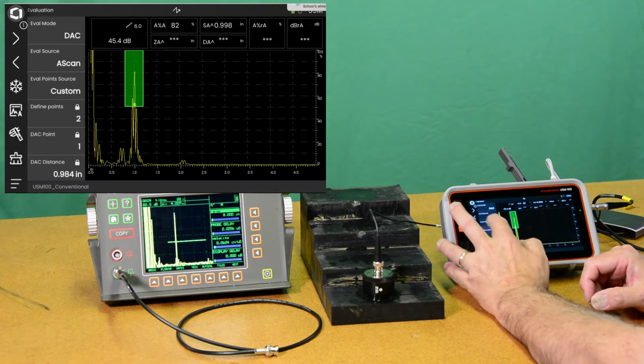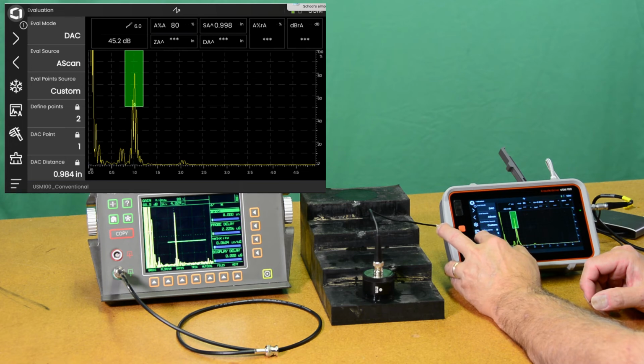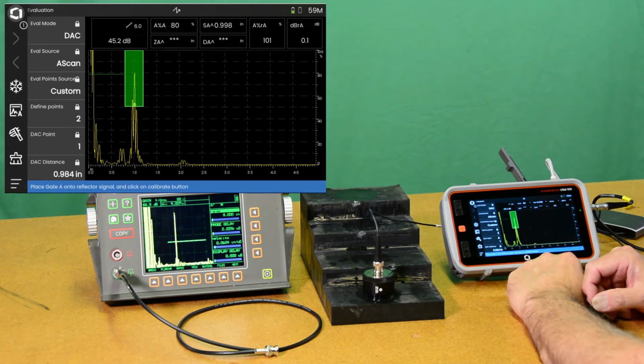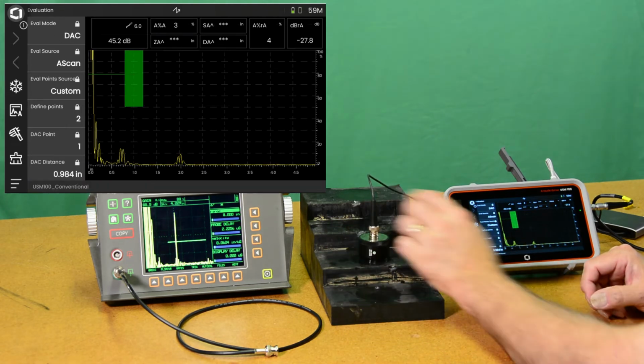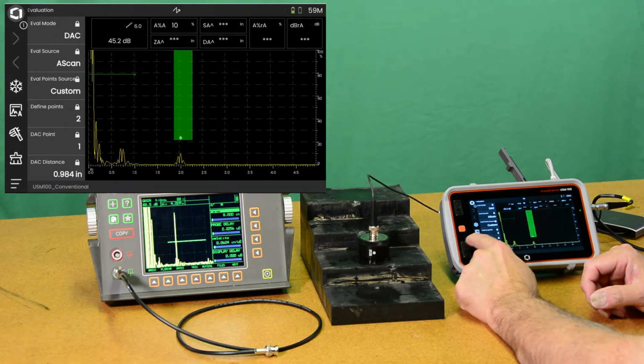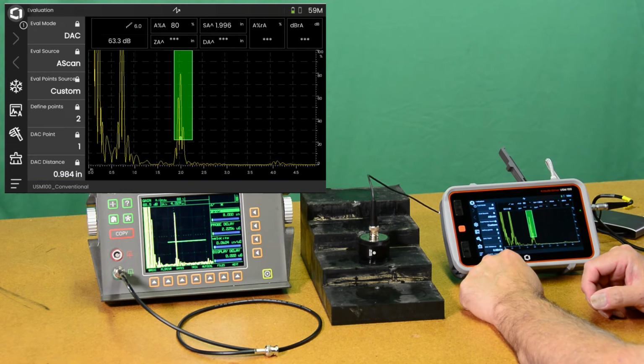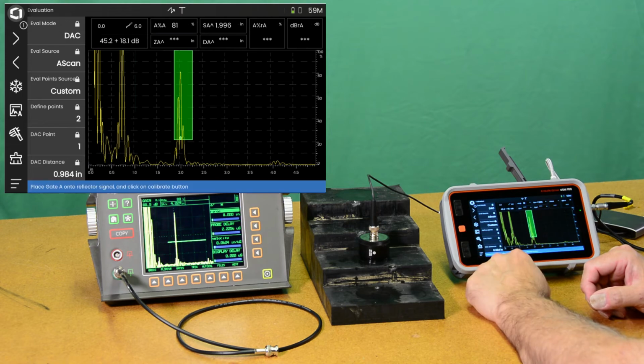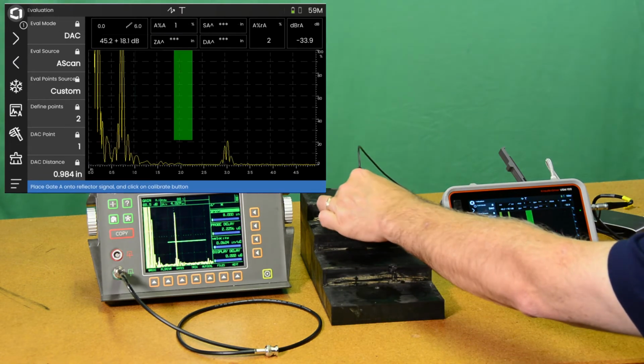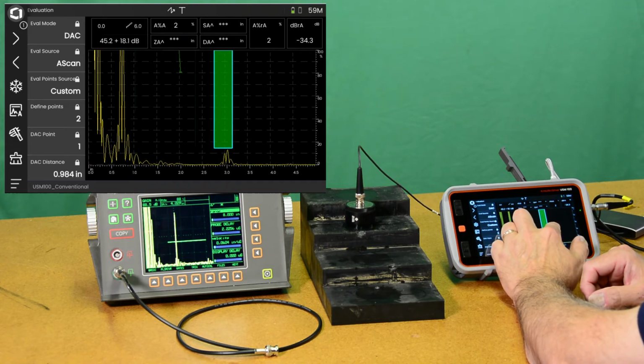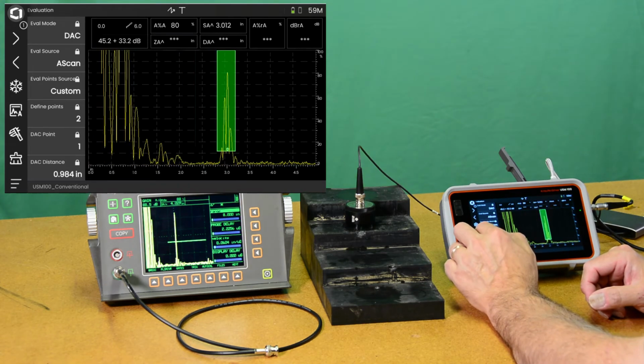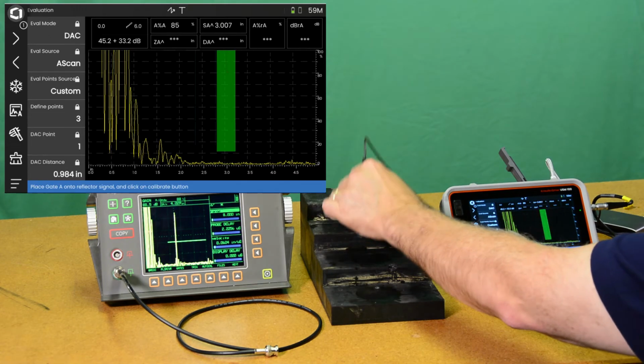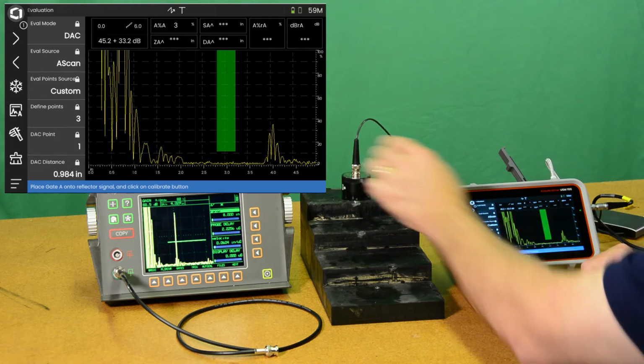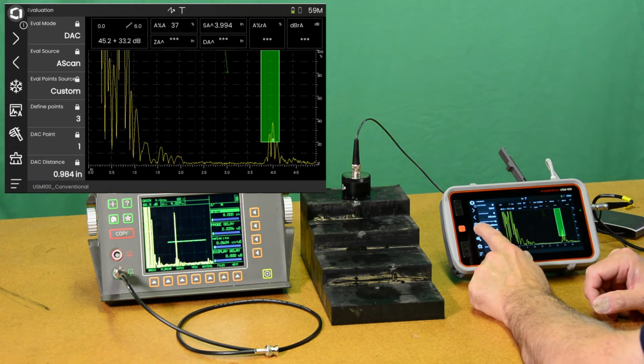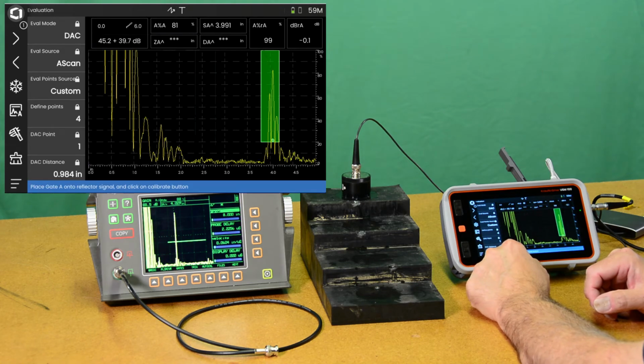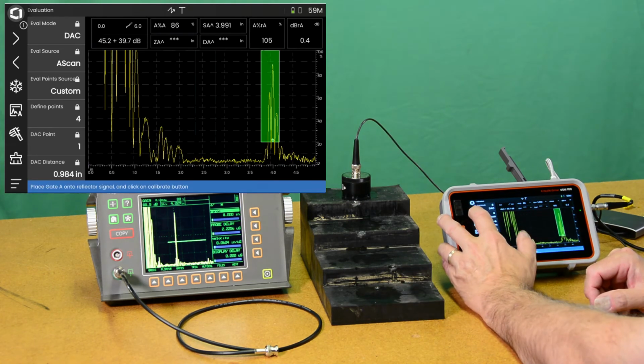So now I can go ahead and record. So if I do auto 80 on that point, I hit record my first point. I see my DAC curve appear. Go to 2 inches. Do auto 80. Record a DAC point. Again, hit the cal. Go to 3 inches. Here. Auto 80. Cal. And go to 4 inches. Cal. Okay, so now I've got a DAC curve showing steps 1 through 4.